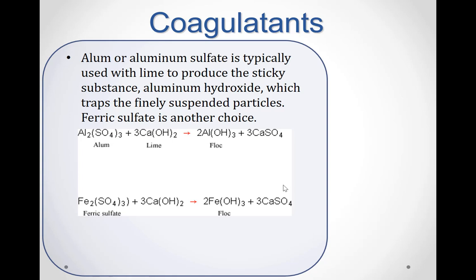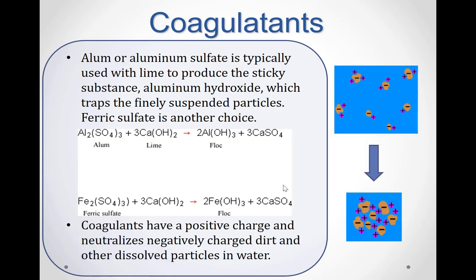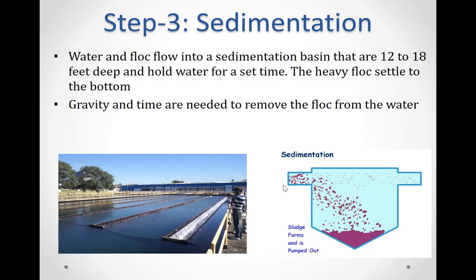Aluminum hydroxide is a sticky gel that traps finely suspended particles, as illustrated in the figure. Step three is sedimentation. During sedimentation, floc settles to the bottom of the water supply due to its weight. In this step, water and floc flow into a sedimentation basin that is 12 to 18 feet deep and holds water for a set time. Gravity and time are needed to remove the floc from the water.